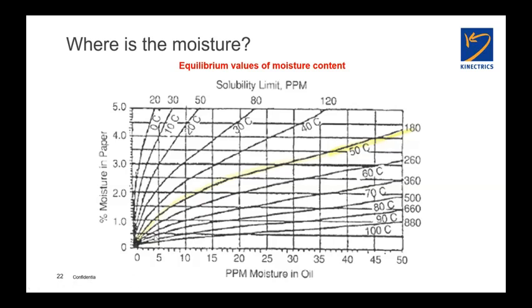Very, very different. So even though the parts per million is less, because we're talking about a lower temperature, it has a much greater effect. And so, again, not to beat it to death, but this is why it's very critical that when you do oil testing in a unit, you absolutely need to know the temperature of the sample at the time it was taken.